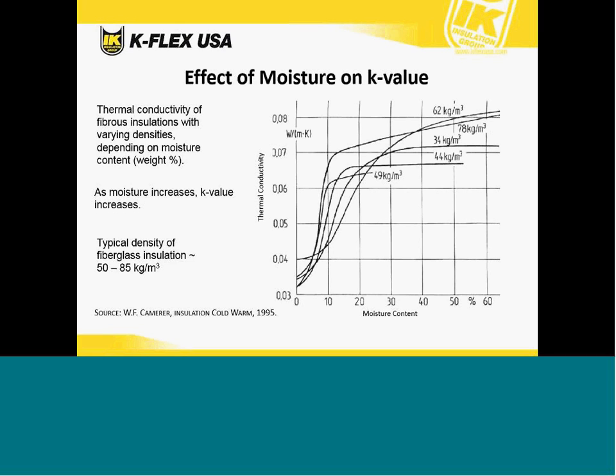A quick analogy for this: I'm sure we've all picked up a hot pan out of the oven with a wet dish rag. If we pick it up with a dry dish towel, we're fine, but if the dish towel is wet and we pick up that pan, we are going to get a burn. That's because moisture conducts heat much, much better than a typical insulating material. The main takeaway here is to keep our insulation system dry so the performance is maintained through the life of that system.